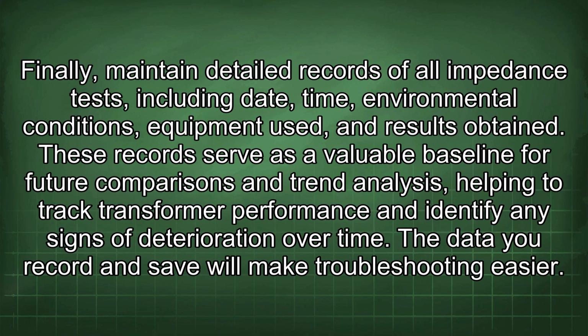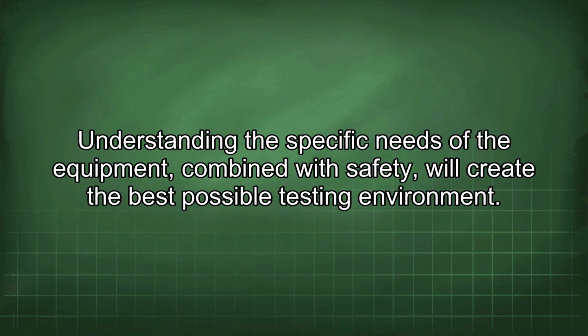issues. Finally, maintain detailed records of all impedance tests, including date, time, environmental conditions, equipment used, and results obtained. These records serve as a valuable baseline for future comparisons and trend analysis, helping to track transformer performance and identify any signs of deterioration over time. The data you record and save will make troubleshooting easier. Understanding the specific needs of the equipment combined with safety will create the best possible testing environment.